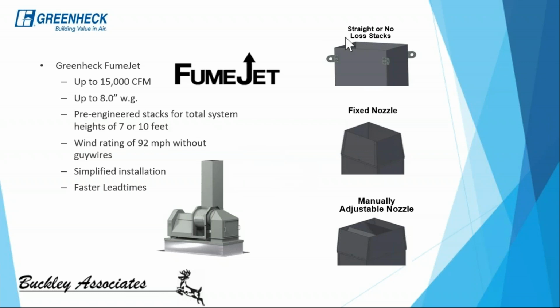Okay, so on top of these stacks, we have different options here. I know I talked about some variable nozzles. We don't have that on this specific line, but we do have a manually adjustable nozzle. So if we're not getting the plume height high enough, we can manually adjust this nozzle to increase the nozzle velocity in the field. Otherwise, we can also add a fixed nozzle just to increase some plume height at the discharge of these fans.